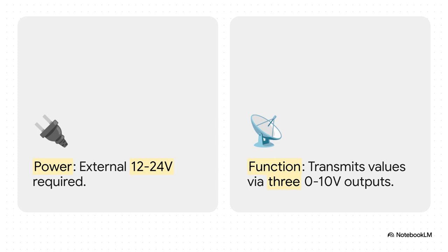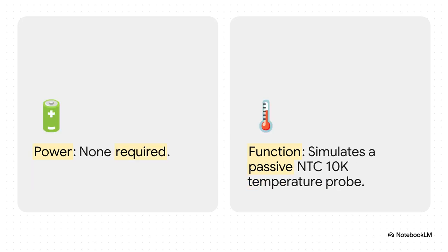Here, it acts just like a classic transmitter, pushing out the temperature, humidity, and CO2 values over its 3 separate 0 to 10 volt channels. This mode, as you'd expect, needs that external power to drive those outputs. And finally, this one is just brilliant. NTC 10K mode. In this mode, it needs no power at all. It just uses 2 terminals to act exactly like a standard passive NTC 10K temperature probe. This is an absolute game changer for retrofitting older systems that are just looking for a simple temperature input without you having to overhaul the whole controller.